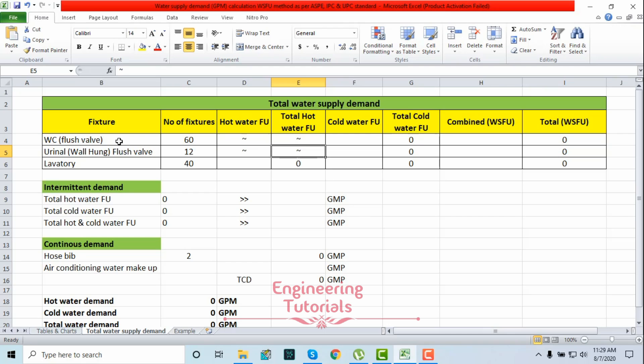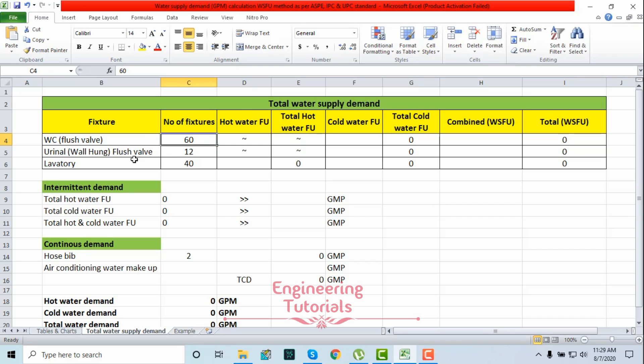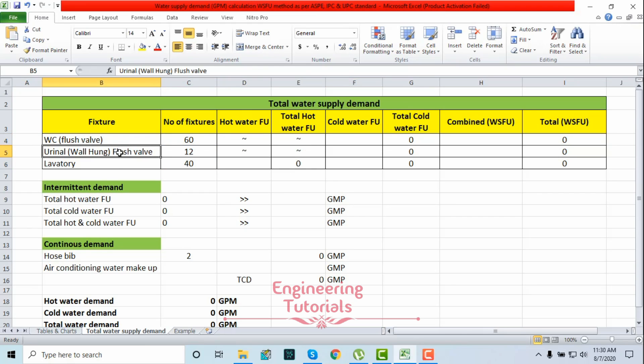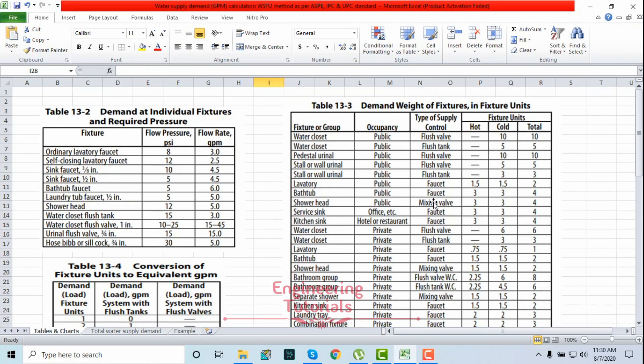Let's say we have an office building and we have a number of fixtures described here: water closets — flush valve type — 60 of them; urinals — wall hung flush valve type — 12; and lavatories — 40. It depends on the number of fixtures in your drawing; you have to write the total number of fixtures. Since we are using the water supply fixture unit method, we have to write the fixture unit value associated with each fixture. Here are the tables and charts I'm going to use.